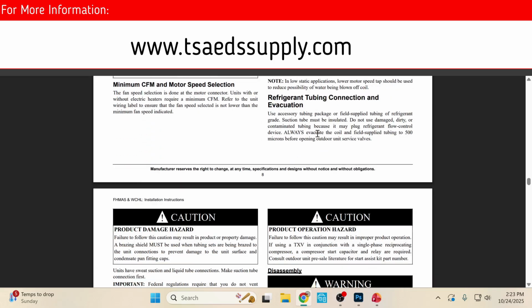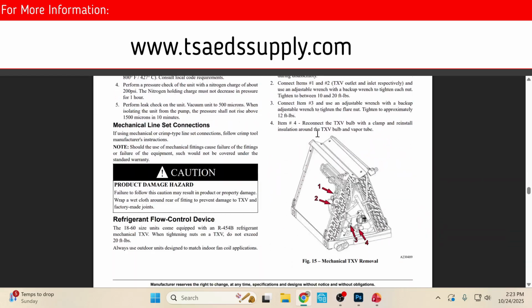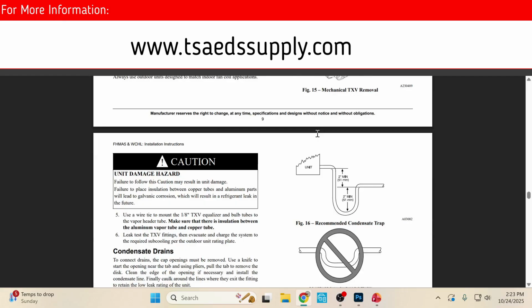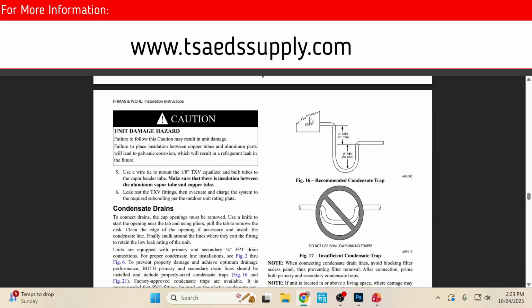And I'm going to move in, see if I can move down this just a little bit. This is one thing here that we will mention at some point in time. Make sure you look at this. This is what a lot of people are using, these run traps or a P-trap. You cannot, this is not a P-trap. This is what they call a U-trap or a J-trap. So you have to have this for everything to drain properly and for the static pressure, because you don't want this drain just dripping.